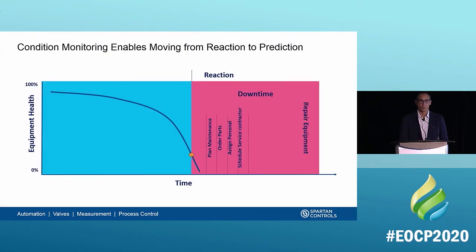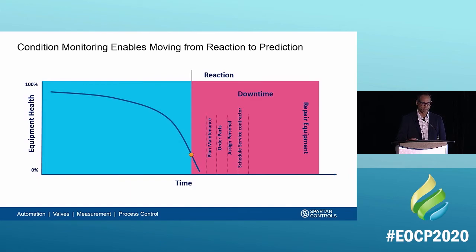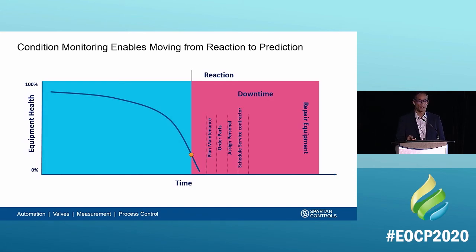So why is condition monitoring so important and how can we leverage it? Let's look at what we call a standard PF curve. On the x-axis is time and on the y-axis is equipment health, from zero to 100%. A 100% means a brand new, completely healthy piece of equipment, while zero means that equipment has failed to the point where it will no longer perform its duty. Over time, once a fault is generated in the machinery, the health degrades until it reaches functional failure — the point at which we must repair it, incurring downtime.